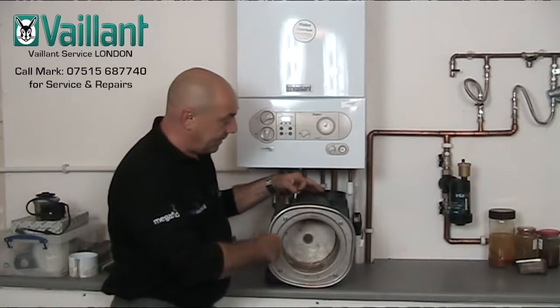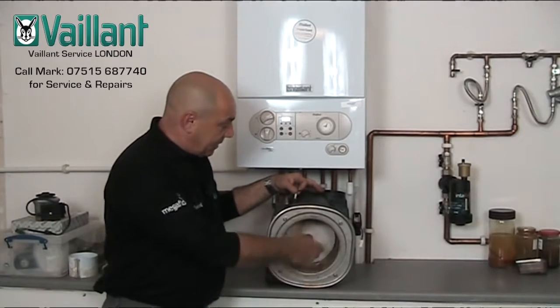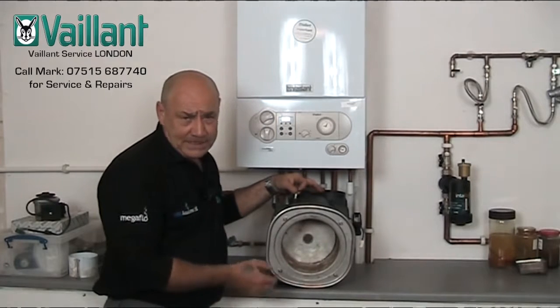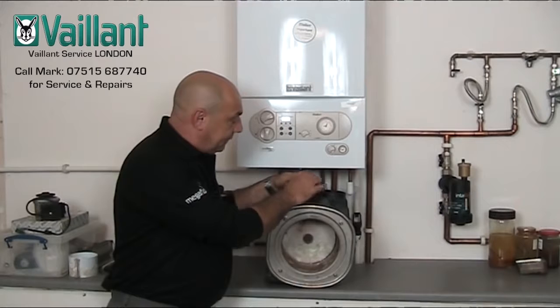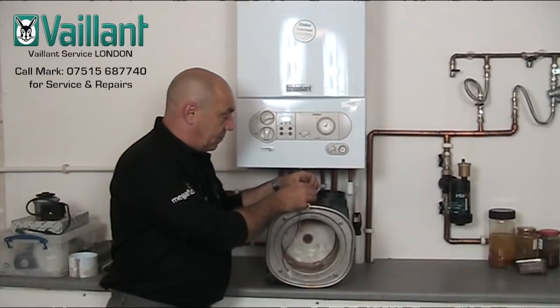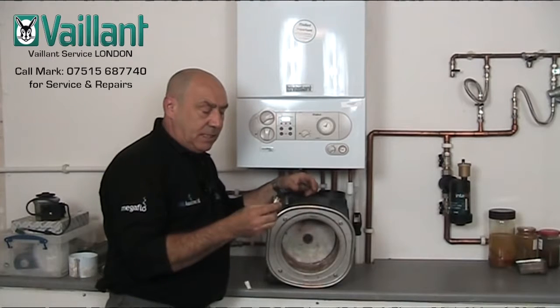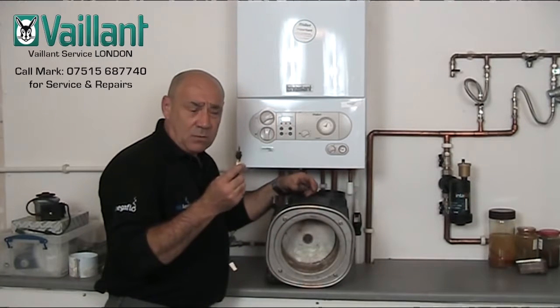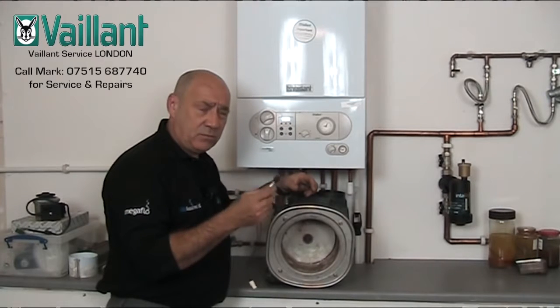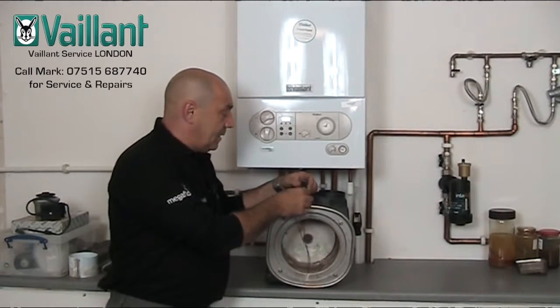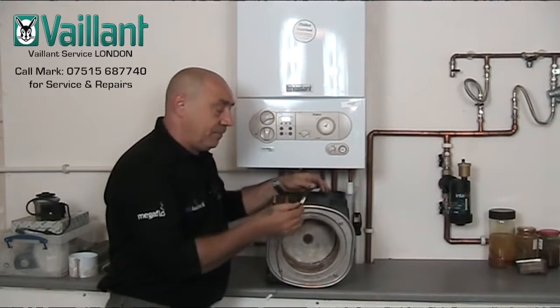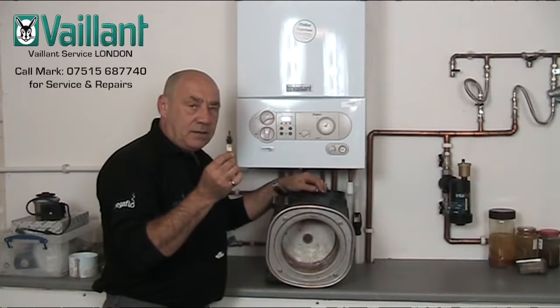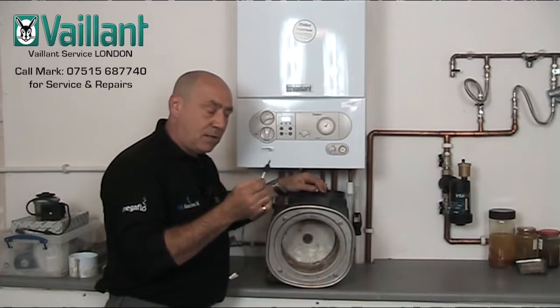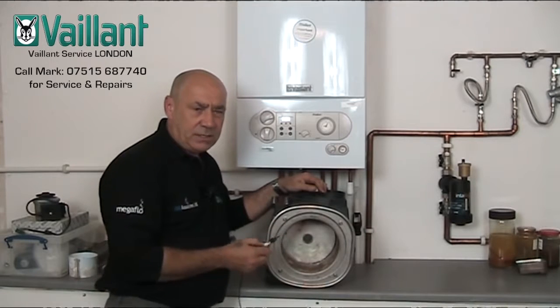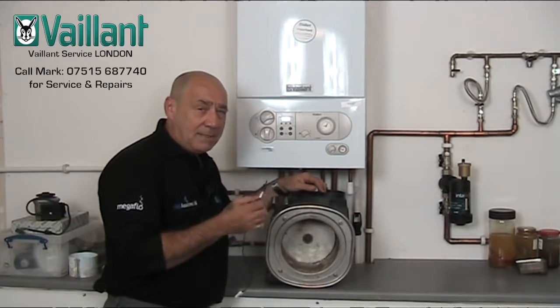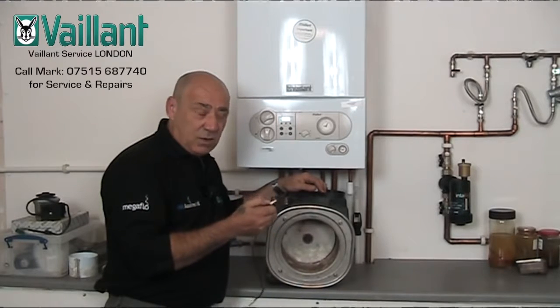Now this continually monitors the external temperature, or the surface temperature and the air temperature around the coils inside the heat exchanger. Now, if for whatever reason your boiler has got no water in it, or for whatever reason it overheats, this particular component will fuse, or it will blow, and therefore you will not be able to reset the boiler, and you will get the fault code F76. Now this is quite catastrophic, because the theory is that if this thermal fuse or link trips or blows, the integrity of the main heat exchanger is in serious doubt, because it's probably been damaged beyond repair, or you can't continue to use it.